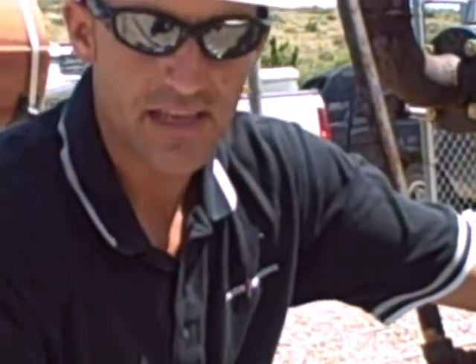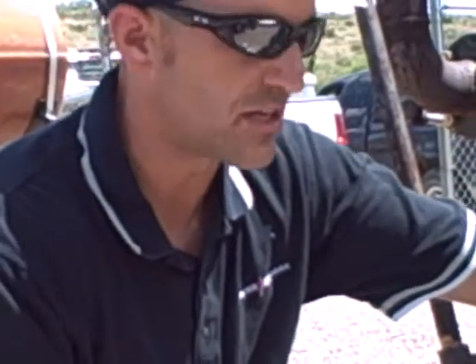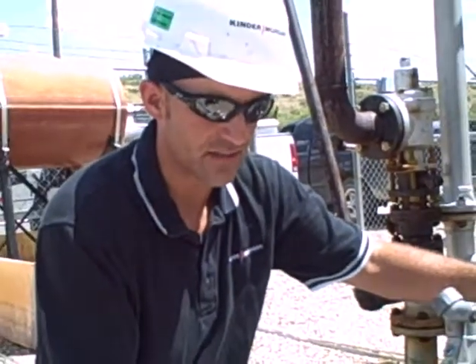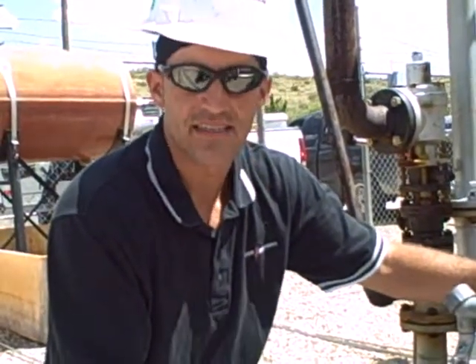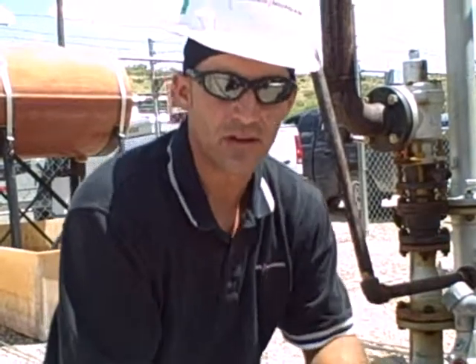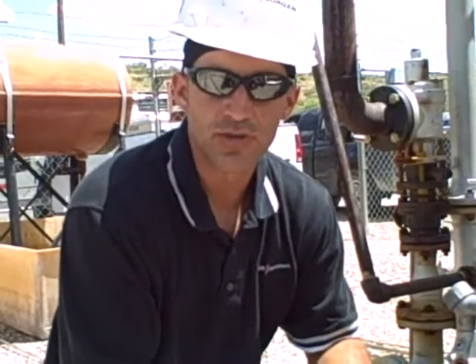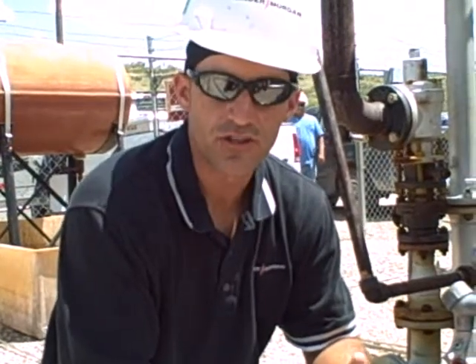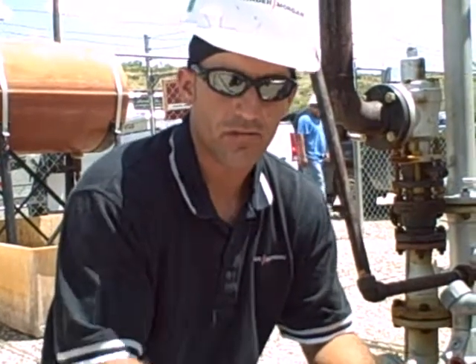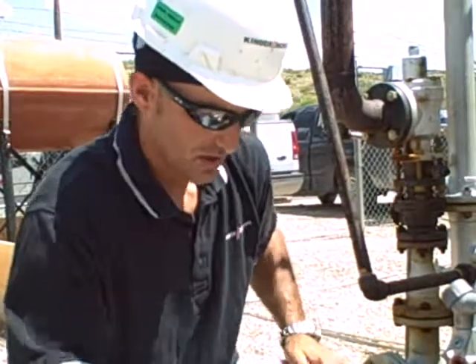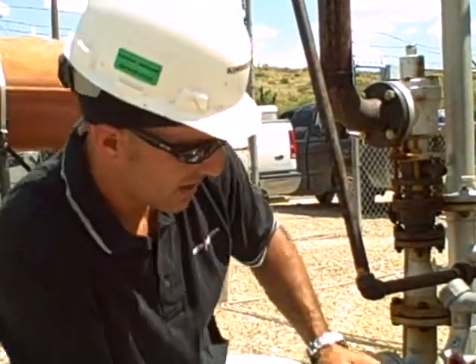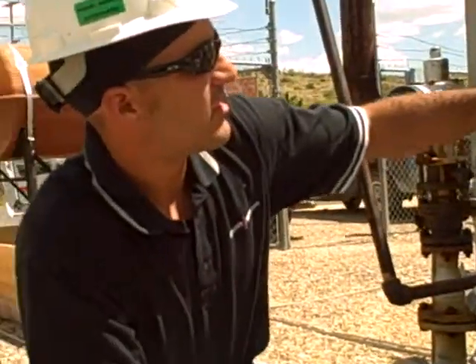Basically the way the BS&W probe works is it measures the water and the oil that's inside of it using capacitance. It then turns it into a 4 to 20 milliamp signal, which we send back to our process logic controllers for analysis by the operators. So we're going to go ahead here and start to calibrate it.